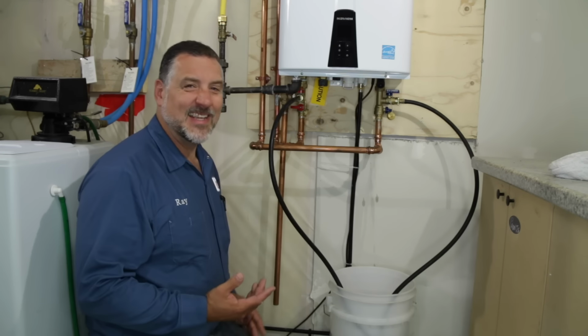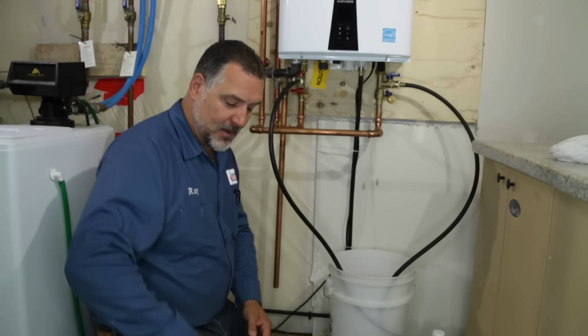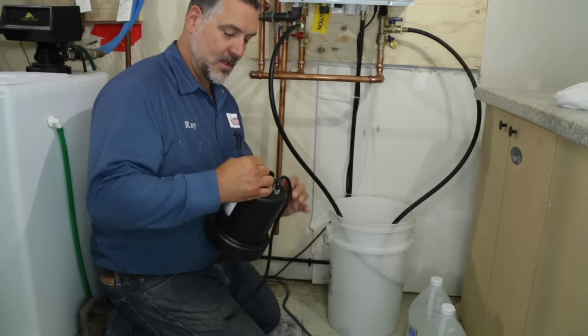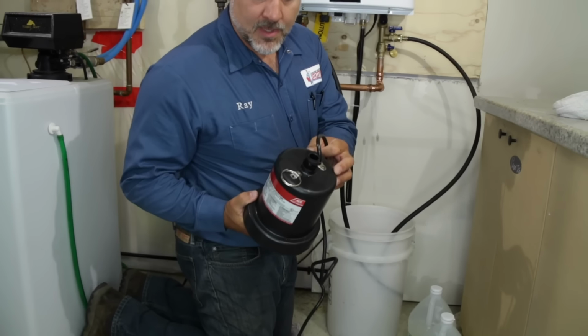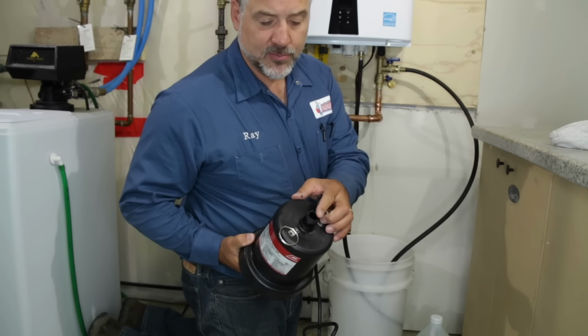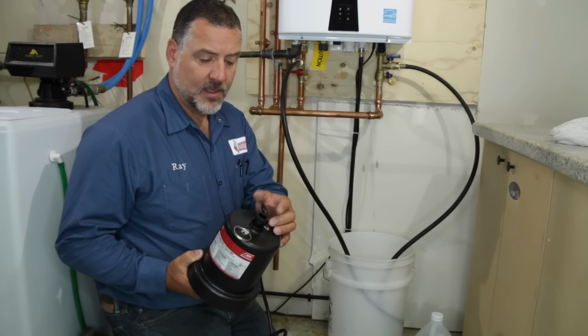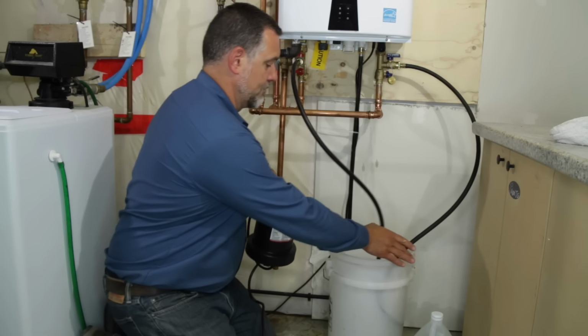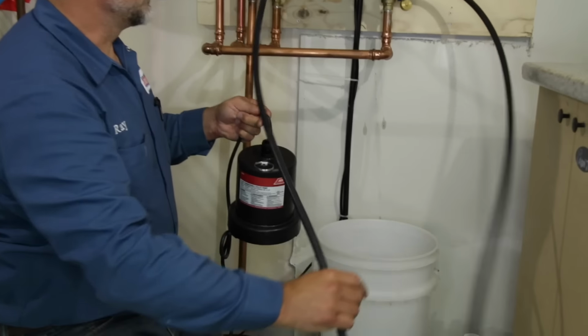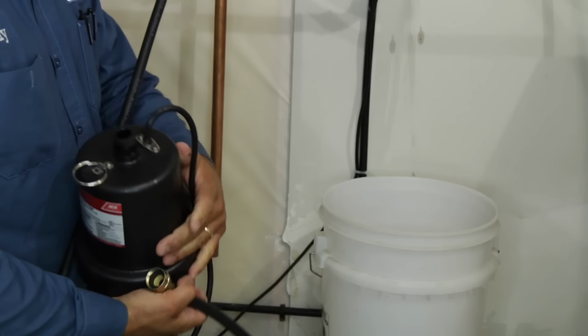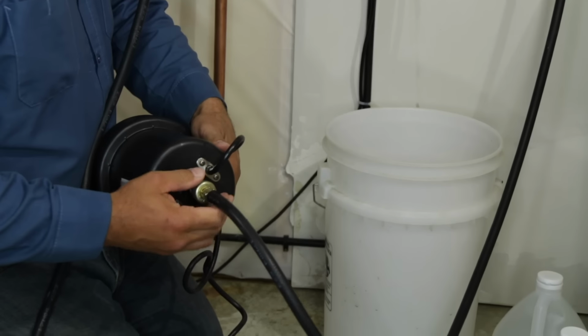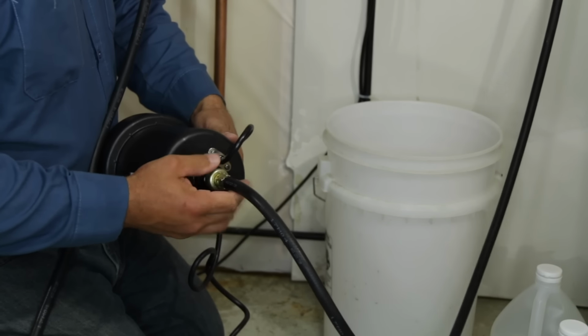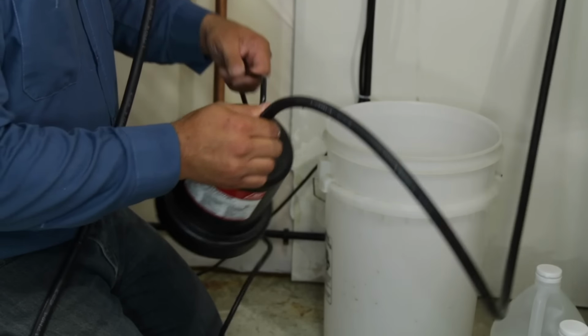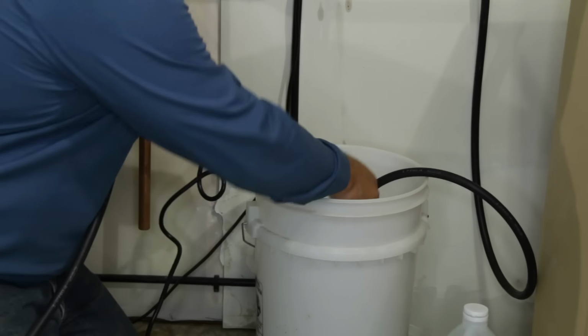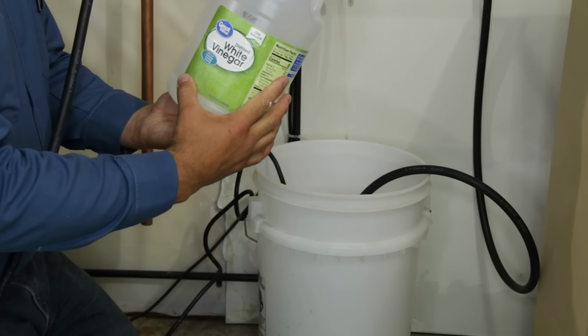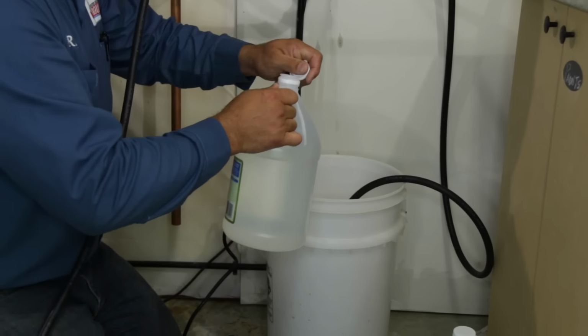Now what's left is to descale the heater. To do that, we have a pump, just a small sump pump. And the thing that's important is that you have a clothes washer hose inlet on your pump. And we're just going to put that inside the bucket. We'll take the cold side inlet, connect it to the top. Tighten that down. Place your sump pump inside your bucket. We're going to take 2 gallons of white vinegar. We're going to dump that in.